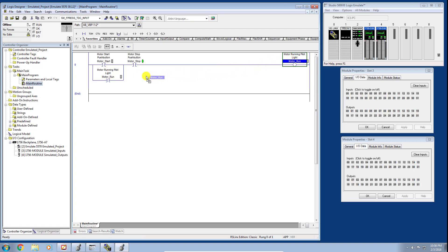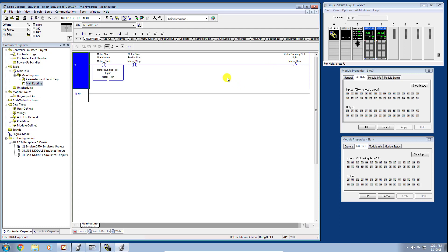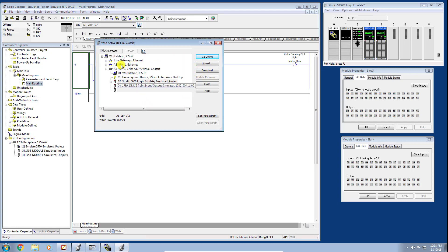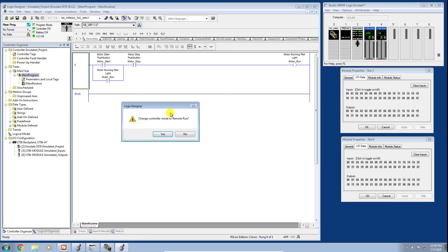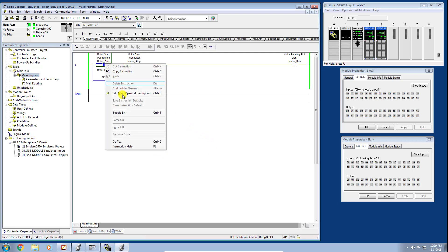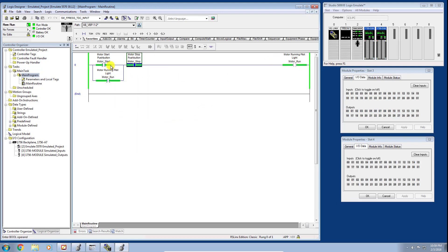We've effectively created a simple motor start-stop push button logic. Note that we haven't assigned any physical I/O — these are internal tags only. We'll save this project and download it to our controller, confirming the correct path using Who Active, then click Download. Once it finishes, we go into Run Mode, toggle the start button on, and you can see it seals in. I can toggle the start bit off and the motor stays running.